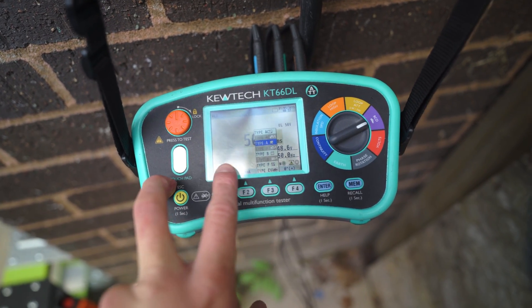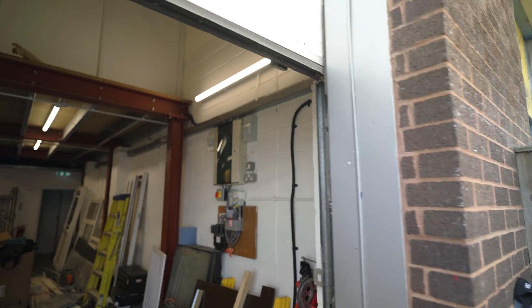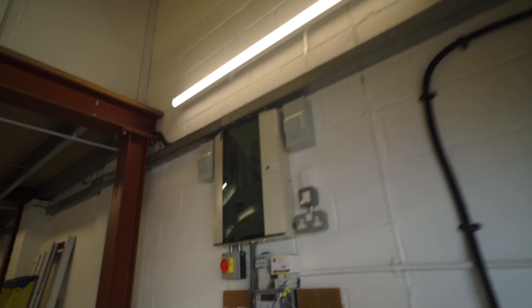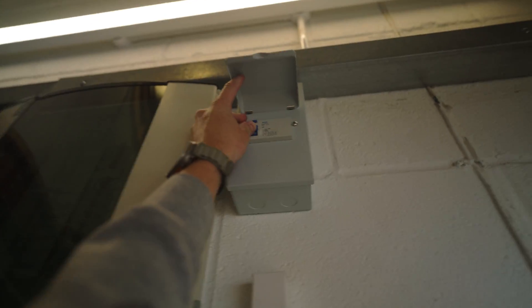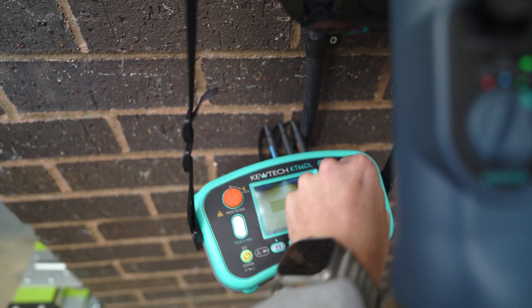Then I go over to Type A with the Kewtech test — that should trip the RCD inside. There we go, flick that back on — 7.8 milliseconds. And now we can do our loop testing, although it's saying fault.